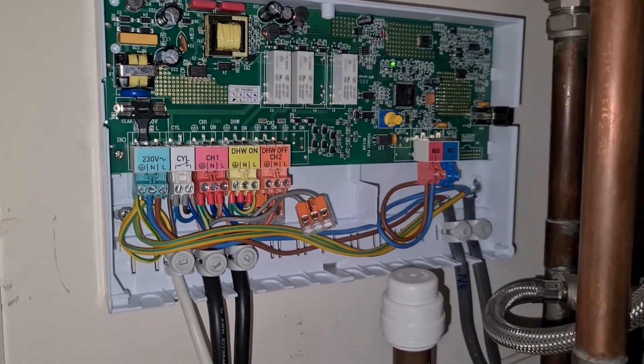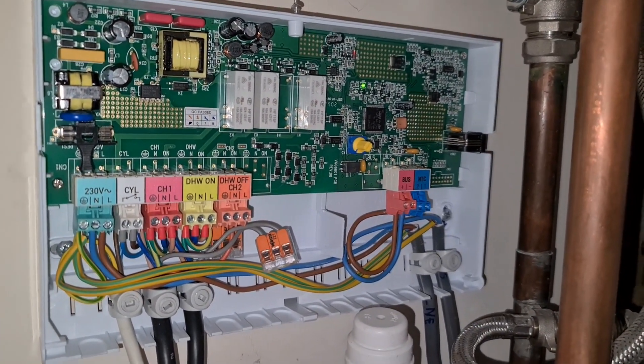This is the Vaillant heater wiring centre that Matthew has been replacing. It was down under these laths with no access to it, and it got absolutely soaked when the tank ruptured, so he's moved it up here. All the wires are nicely dressed and clamped in — a neat, tidy job. They come with these little pin terminals that you wire onto the ends of the leads and then pop them in. Matthew had to reposition a few bits from where they were, and we're now just running through some live tests to make sure it's all switching properly.